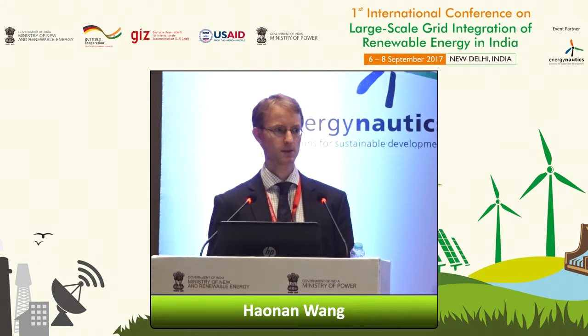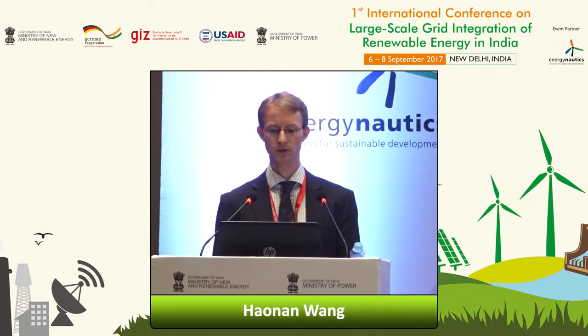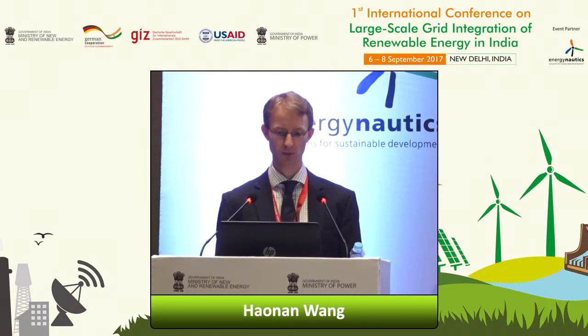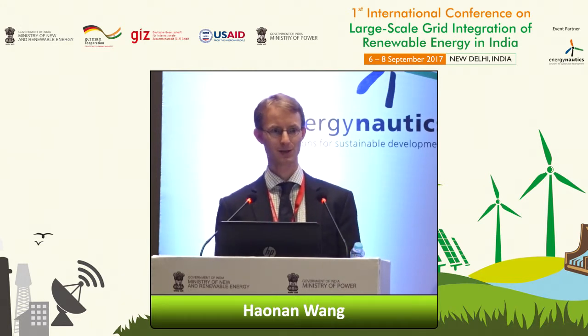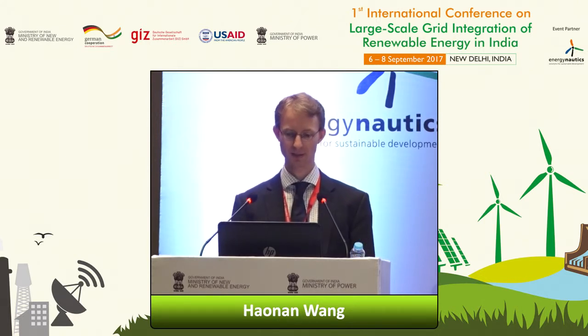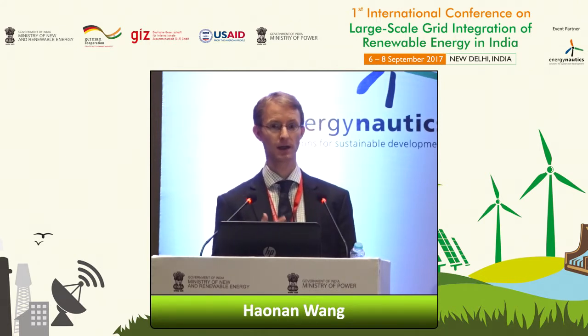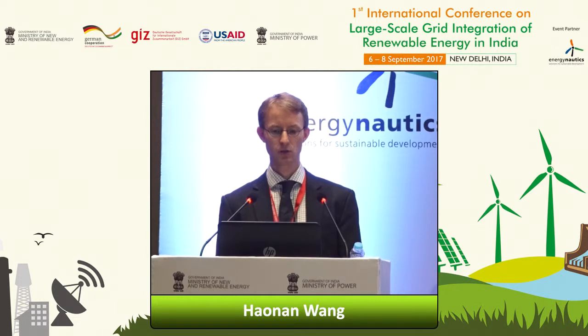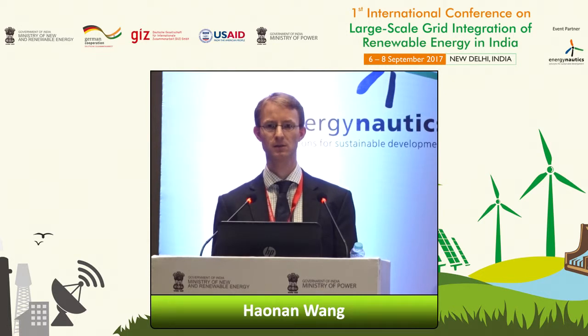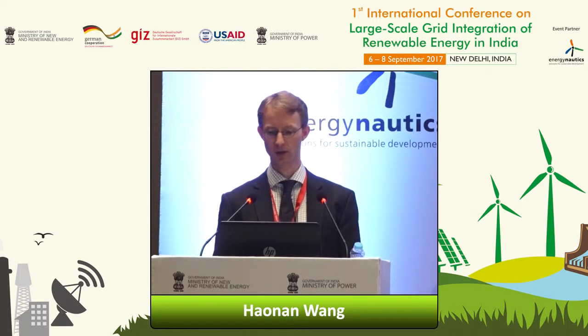So considering these kinds of concepts, we are applying a deployment strategy in different projects. That means we first talk about the concept, and we design it according to the requirements. Every grid operator has its own ideas and specialities. We then go into an offline simulation, analyzing what I just showed, with technical and economic analysis. Then we go into real-time simulation, which means we design a controller and test if the controller operates stable and does what it should in real-time simulation, including in the controller-in-the-loop configuration. And finally, it goes into the field.